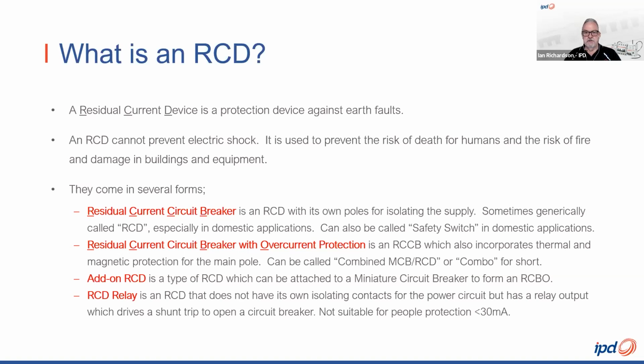The RCD relay will often have a separate external toroid, which can allow a variety of cable sizes for the power cables to be protected. And that can be quite convenient in some installations. RCD relays have an adjustable sensitivity and adjustable time delay functions. But we've got to be careful. The wiring rules tell us that we have to use a fixed setting RCD, not exceeding 30 milliamp, when we're talking about people protections. So this really means that we cannot use an RCD relay for final sub-circuit residual current protection.